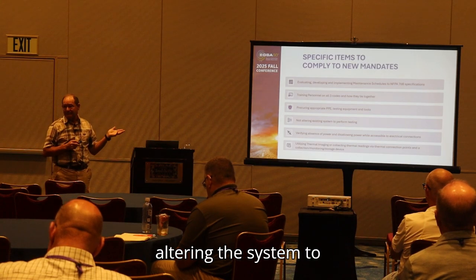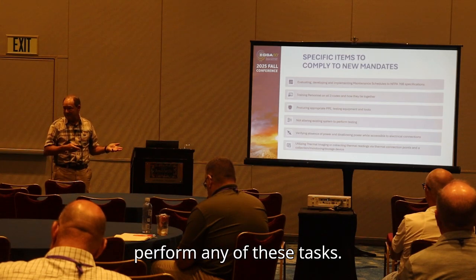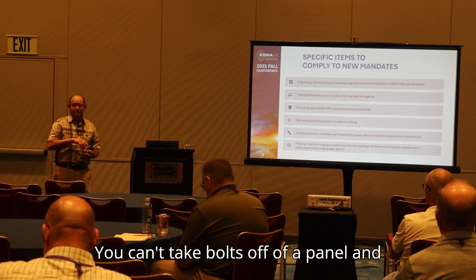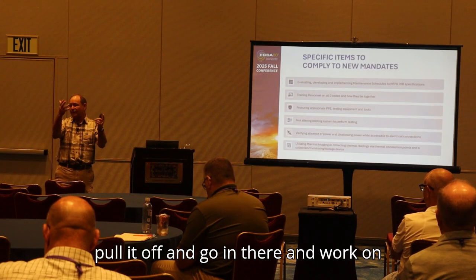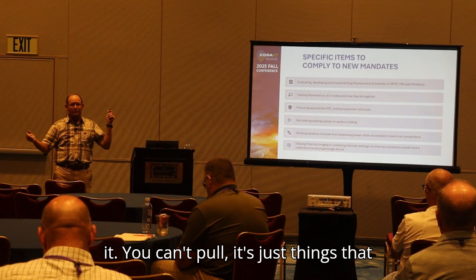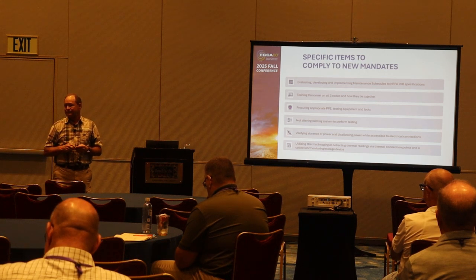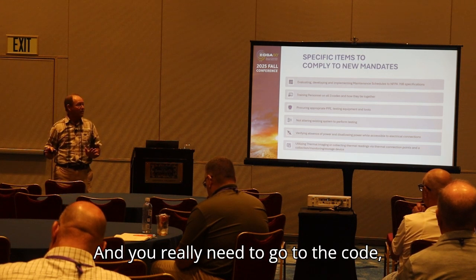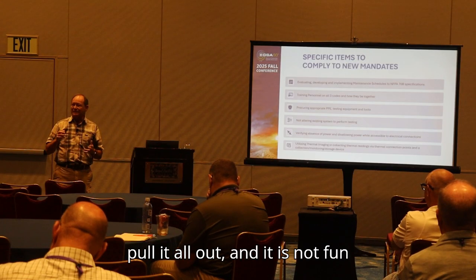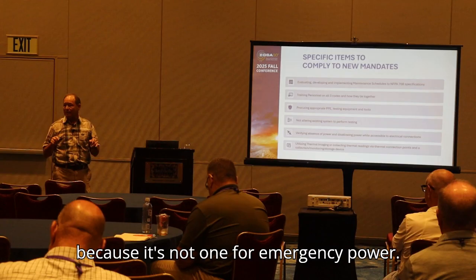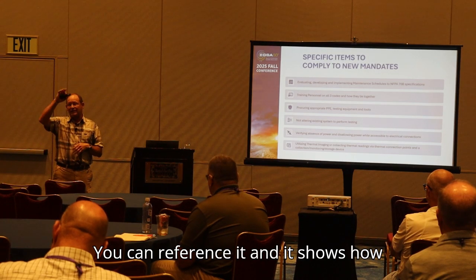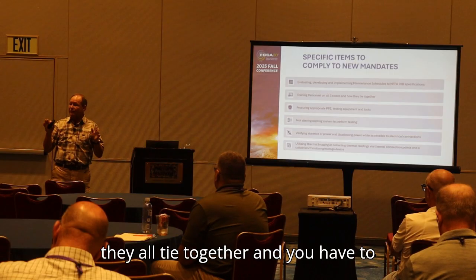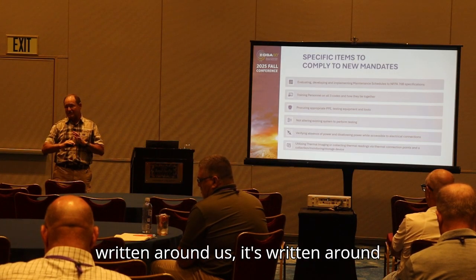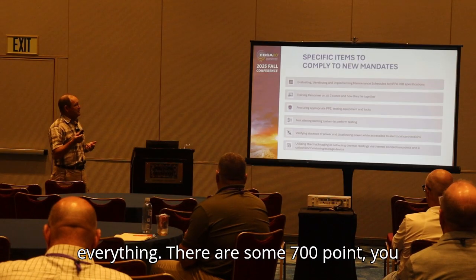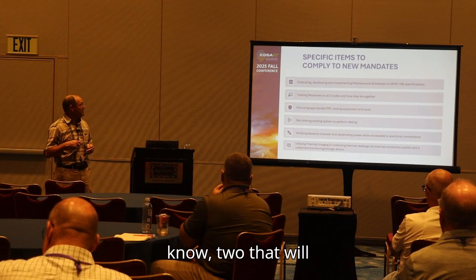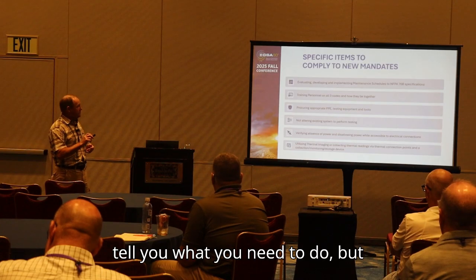Not altering the system to perform any of these tasks. You can't take bolts off of a panel and pull it off and go in there and work on it. There are just things that you can't do. And you really need to go to the code, pull it all out, and it is not fun because it's not written for emergency power. You can reference it, and it shows how they all tie together, and you have to look at it. It's not written around us, it's written around everything. There are some 700-2 sections that will tell you what you need to do.